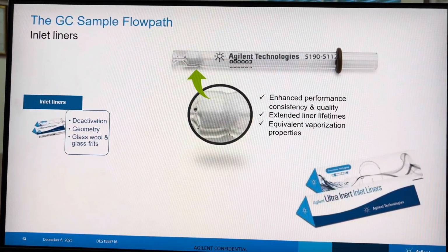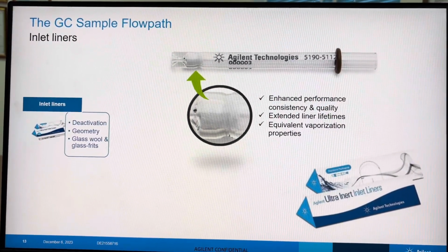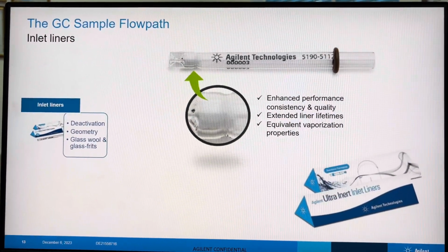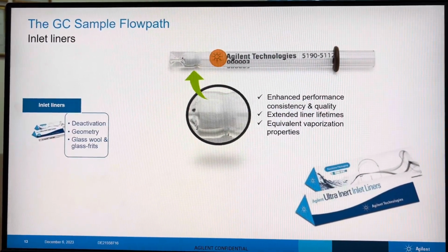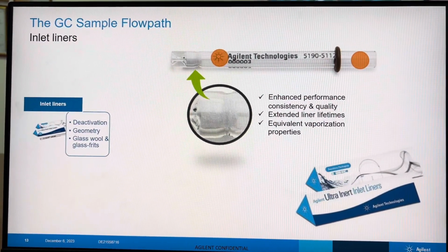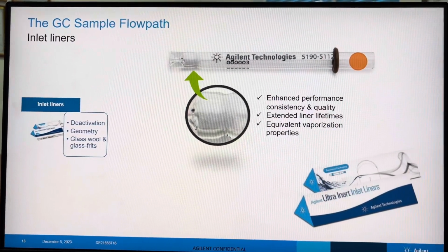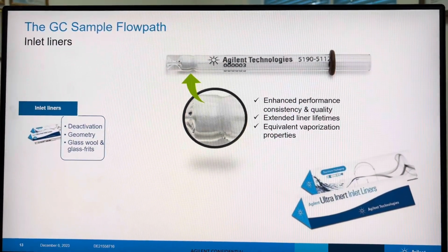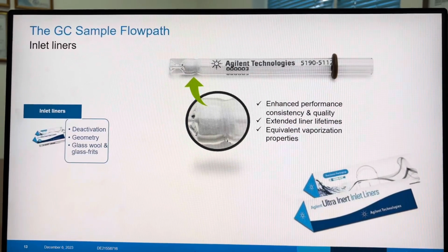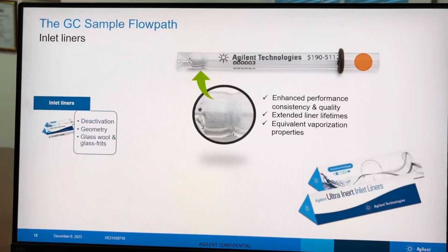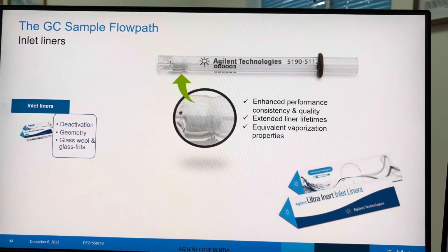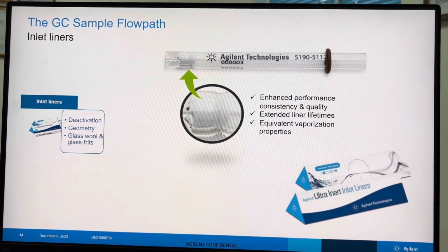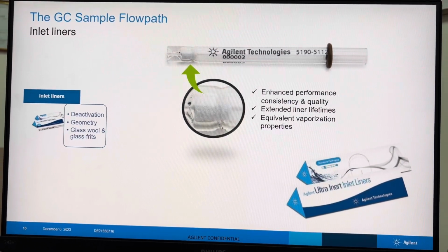Is the total liner volume sufficient to take care of that volume or not? If the expansion volume of the sample solvent is more than the liner capacity, what will happen? Our results are irreproducible. Especially you might see area variations from run to run. That's the reason the volume should be within the liner volume.